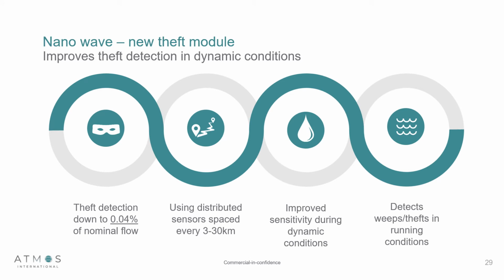As well as the new fast scanning module and the new hardware solutions that Atmos has to offer, we've also developed a new theft module that we call Nano Wave. During the discussion, I said there was an advantage to having multiple pressure sensors along your pipeline. By doing that, you have the ability to cross-check data, and you're able to see much smaller changes of pressure. This, in essence, is what the Nano Wave module is about. It was designed to improve theft detection in dynamic conditions, because thieves can open the valve very, very slowly in dynamic conditions, which creates a very small change in pressure, which can often be masked by the operations on that pipeline.